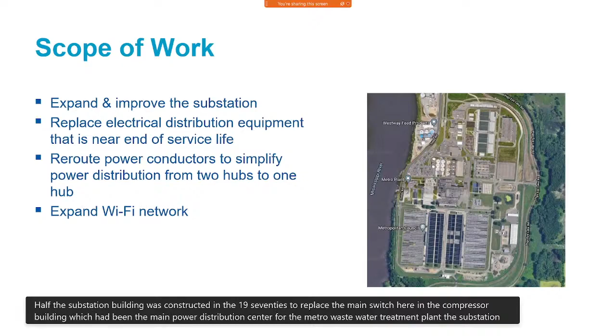In the photograph, the substation building is located adjacent to the Xcel substation, shown in the lower right-hand portion. The substation building was constructed in the 1970s to replace the main switchgear in the compressor building, which had been the main power distribution center for the Metro Wastewater Treatment Plant. The substation is the primary building distributing 13.8 kilovolt power throughout the plant, configured with 4 buses, each connected to incoming power from Xcel Energy.